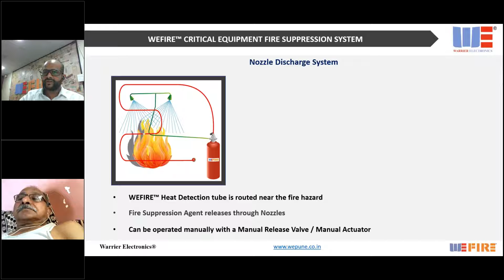Let's look at nozzle discharge system. As I said, there are two types of system. One is a tube discharge system and the other is a nozzle discharge system. In a nozzle discharge system, the principle is the same. Linear heat detection tube is routed within the hazard. As soon as there's a fire, the detection tube will rupture at a particular temperature and open the differential pressure valves on the cylinder. And through the nozzles, through the discharge pipe, the gas will flow directly on top of the fire. Now, a nozzle discharge system can also be operated manually. So if an operator sees a fire before the system activates on its own, he can always activate it manually. Let's look at a live demo.